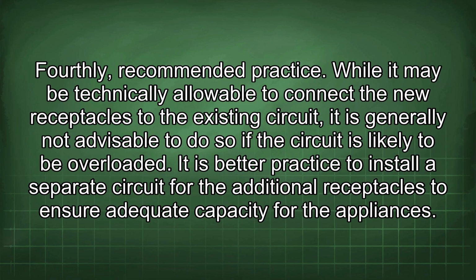Fourthly, recommended practice. While it may be technically allowable to connect the new receptacles to the existing circuit, it is generally not advisable to do so if the circuit is likely to be overloaded. It is better practice to install a separate circuit for the additional receptacles to ensure adequate capacity for the appliances.